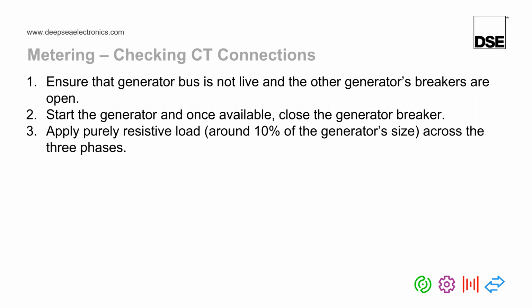So one thing you could try doing is maybe renting a single phase load bank to do these tests. It just takes a little bit longer because you'd have to test each phase individually rather than testing all phases at once. Though, in all honesty, it doesn't actually have to be a load bank itself. I've actually done this setup procedure myself without using a load bank, by making my own load bank using electrical heaters, effectively anything that is purely resistive.